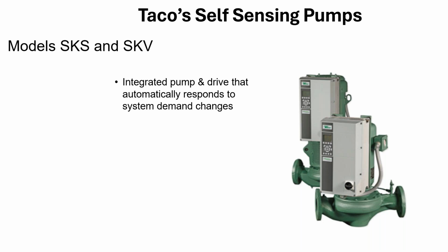Variable speed, and somebody puts a transducer out there, has to run all that wiring back to the drive so it speeds up and slows down, right? Based on the system changes. You don't need any of that with these drives, okay? Now, I'm not going to do the deep dive into how that all works. I'll explain it a little bit, but nonetheless, they automatically respond to system changes out in the field. So you don't need any remote sensors. That could be a big selling point on some projects.